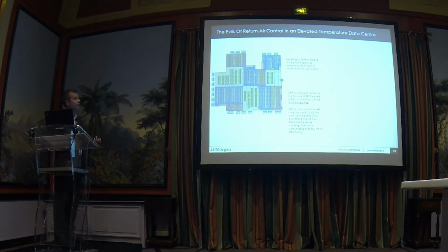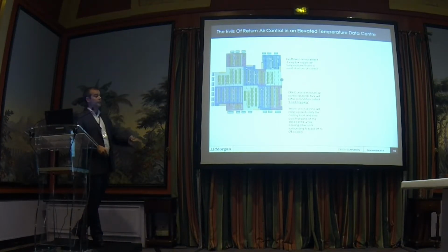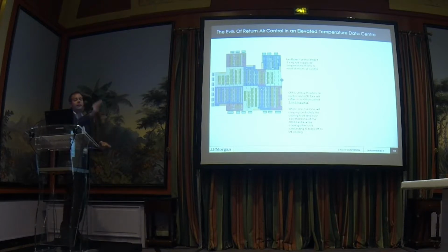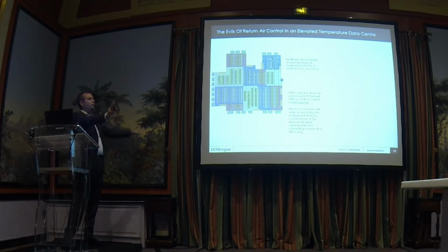Crack units with the return air control of these fans will suffer a condition which I've called load hopping. The moment you turn an air conditioner off on return air control and you turn it back on, the other one's ramped up next to it. The one you turn on and off was running at 100% for a week. This one will now run at 100% for a week because its air movement has increased. It's pulled the heat away from that one there.